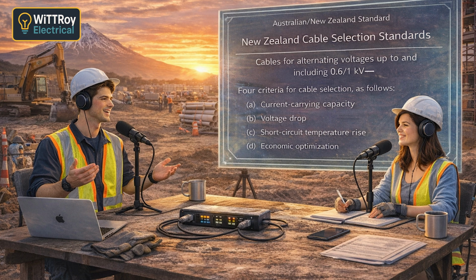Good. Now we move to voltage drop. Right. This one I kind of understand, but I'm not confident. That's fine. Let's build it slowly. Voltage drop means the voltage at the load is lower than the supply. Because some voltage is lost in the cable. Exactly. So what causes that loss? Resistance and impedance of the cable. So longer cable means more resistance. Yes. And more current means more voltage drop. Exactly. So both length and current matter. Yes, those are the big ones.